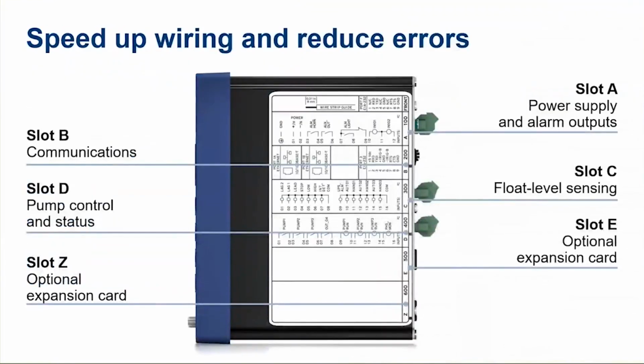So let's talk about what it takes to wire this product up. The picture you see here is the side of the product, and you can see that it's a slot-based chassis. You have 5 different slots on the product. I'm sorry, 6. And you have the pre-labeled I/O that allows you to know exactly where to wire up the inputs and outputs to control that lift station. So let's take a closer look at what that looks like.